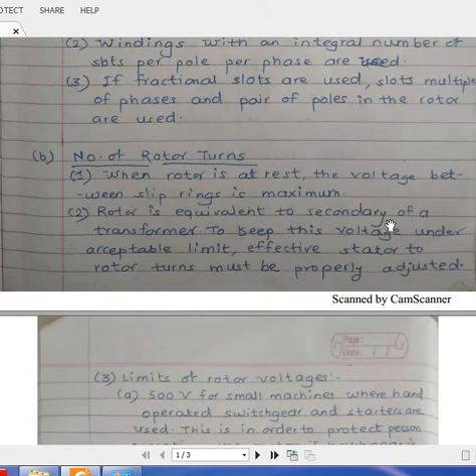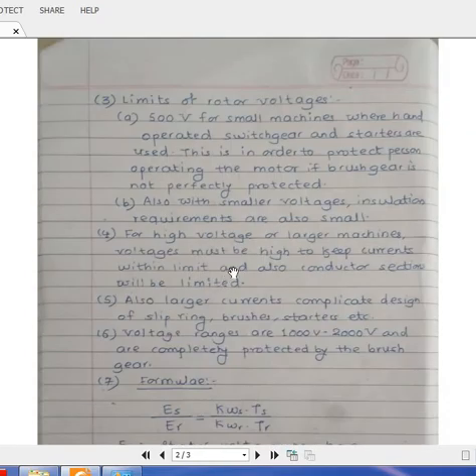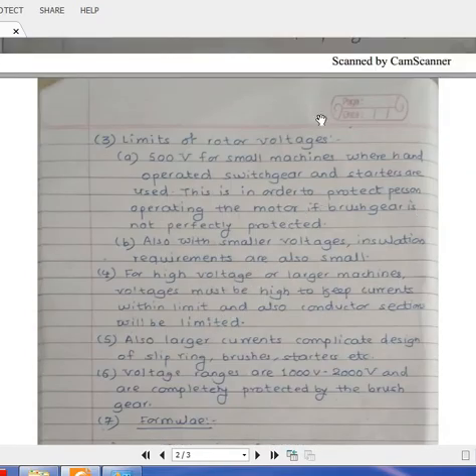When you want to keep your rotor voltage in the induction motor under acceptable limit, you have to consider effective stator to rotor turns. Those must be properly adjusted. The main important point is when the rotor of wound rotor induction motor is at rest, the voltage between slip rings is maximum. So it is a kind of no load.